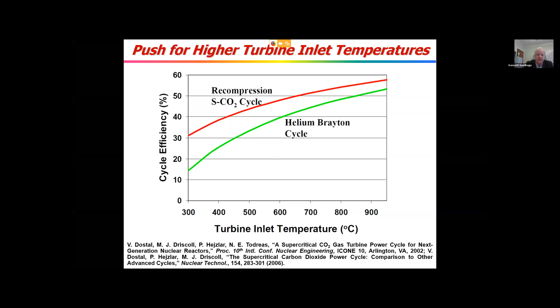So one of the challenges in doing that is the heat exchanger. A very effective type of compact heat exchanger is called a printed circuit heat exchanger. They're currently made out of metal alloys like stainless steels—you can see some photographs of this type of heat exchanger. They're very thin sheets of metal that have been patterned into channel patterns, as you see on the upper right, typically by a chemical etching process, which itself is kind of slow and somewhat expensive.